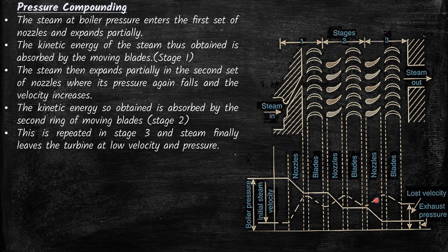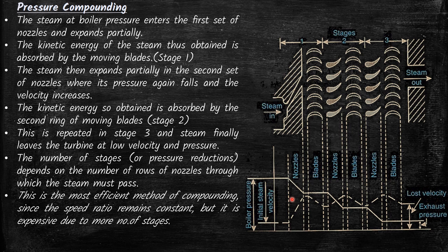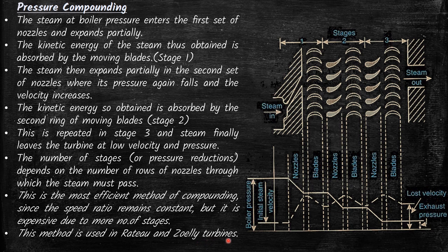The same process is repeated as the steam moves over the third stage. The number of stages — or pressure reductions — depends on the number of rows of nozzles through which the steam must pass. This is the most efficient method of compounding since the speed ratios remain constant, but it is expensive due to the greater number of stages. This method is used in Rateau and Zoelly turbines.